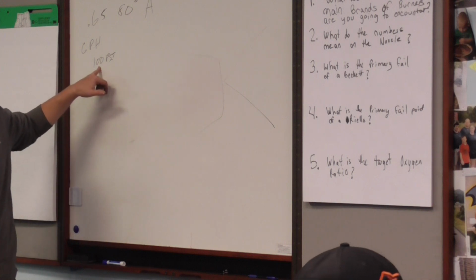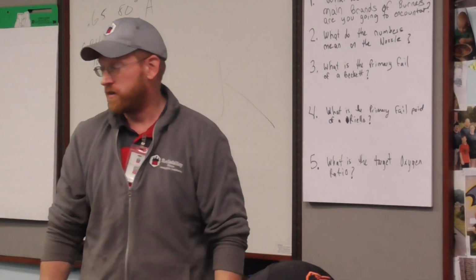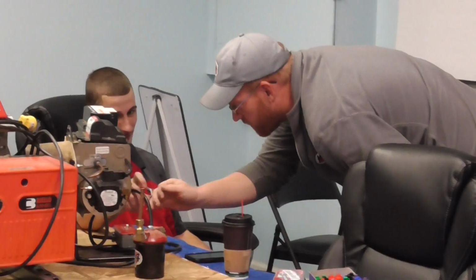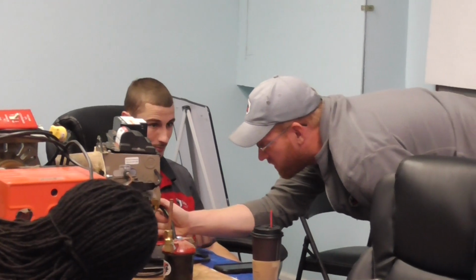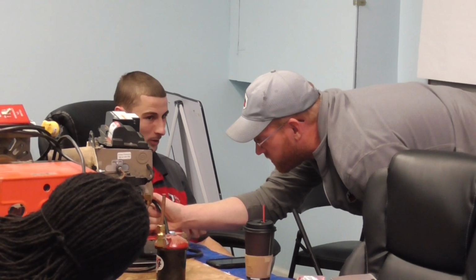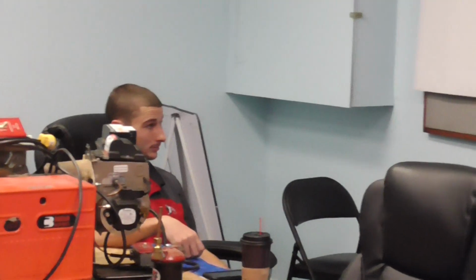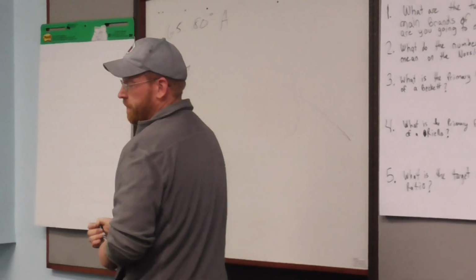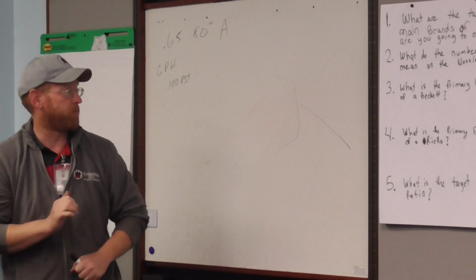The 100 psi generally doesn't matter because most of these run about 125 psi, and the new Beckett's about 140. This nozzle is 0.65 even. That's what this one actually says on it. Most of them don't. Even still, the burners get changed and they'll have a range to them. So go by whatever's on the plate. Whatever you take out, put back in.